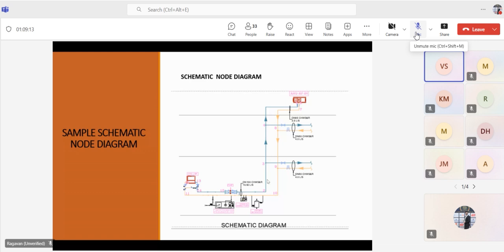Okay, and one more question. Yeah, that is also the same point. I think Mr. Dan has asked the question of how to find out the flow rate for this system. You answered that now: from the cooling load calculation we will find out the load. I am asking about the flow rate for the friction losses. For example, we will know the flow rate of the entire system, but when there is a reduction at point number 3 and the diameter is reduced to DN80, what should be the flow rate at DN80? How do we calculate the flow rate at that particular point?